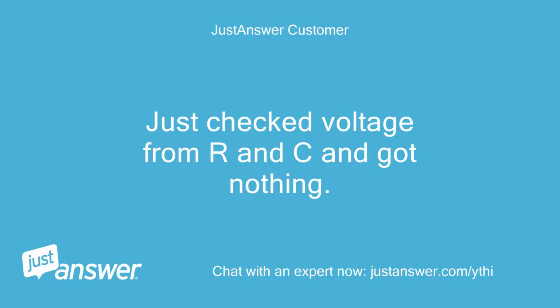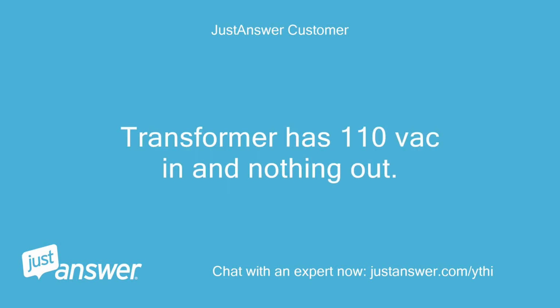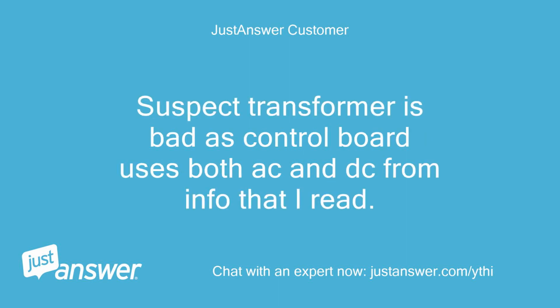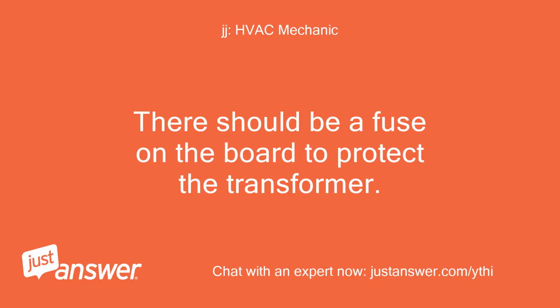Just checked voltage from R and C and got nothing. Should be 24 V. Transformer has 110 going in and nothing out. Suspect transformer is bad as the control board uses both AC and DC from info that I read. I disconnected the thermostats and jumped R to W and nothing happened. There should be a fuse on the board to protect the transformer.